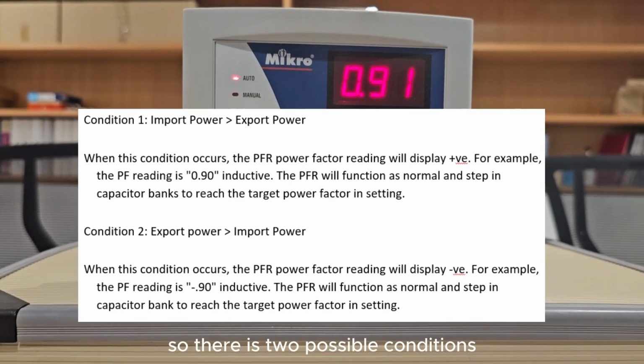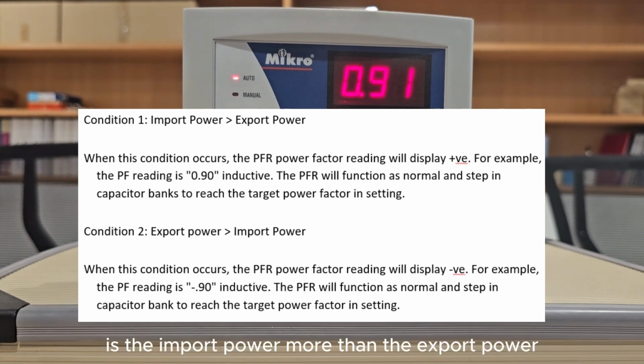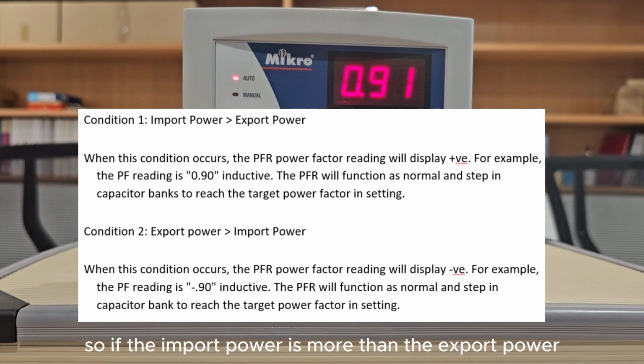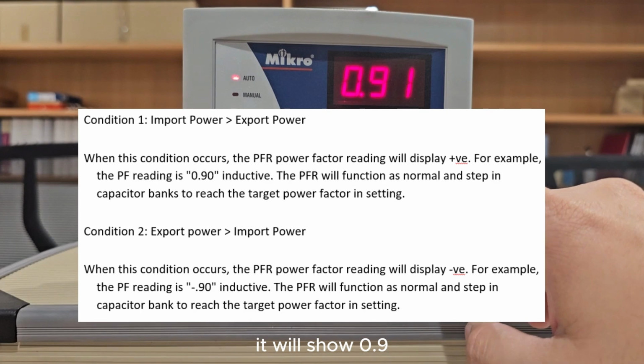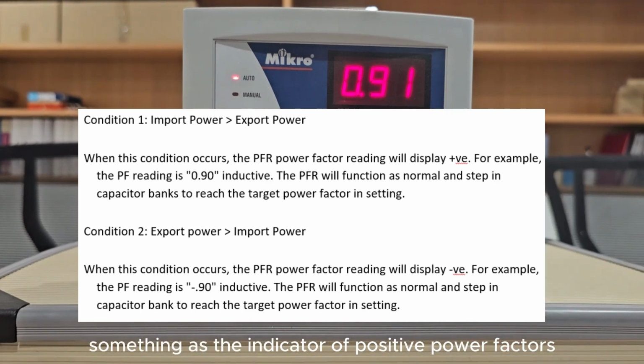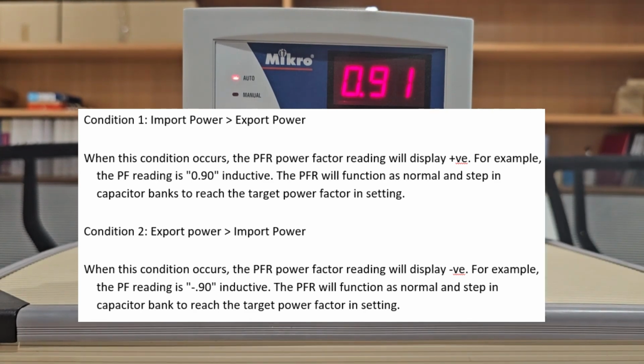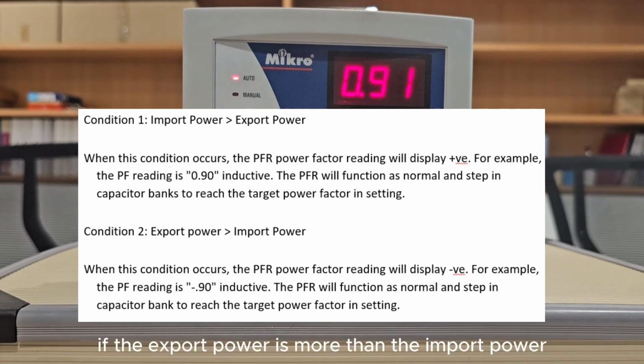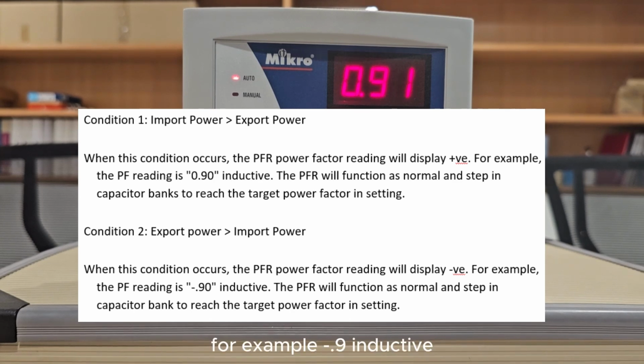So there are two possible conditions that may occur after the solar is turned on. First, the import power is more than the export power, or the export power is more than the import power. If the import power is more than the export power, it will show 0.9 something as the indication of positive power factor. If the export power is more than the import power, it will show the negative sign, for example, negative 0.9 inductive.